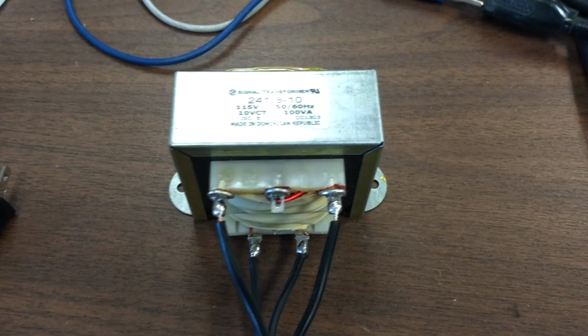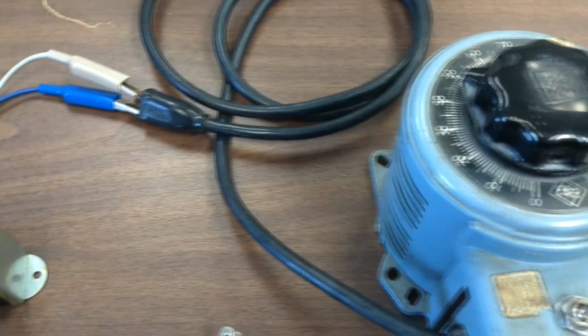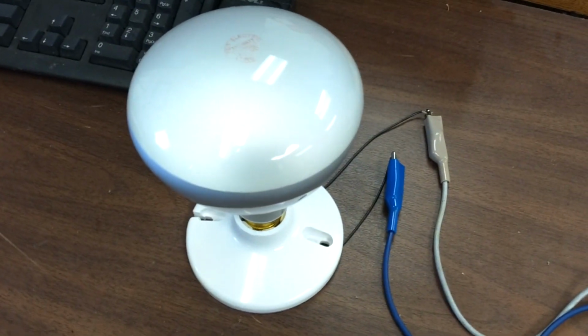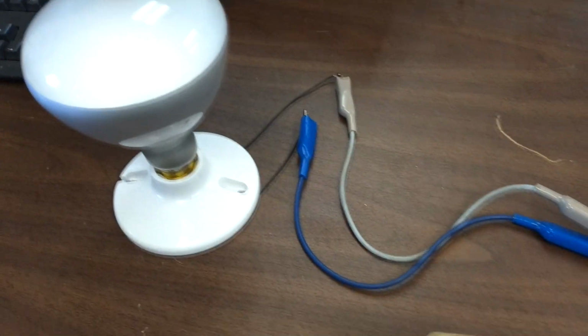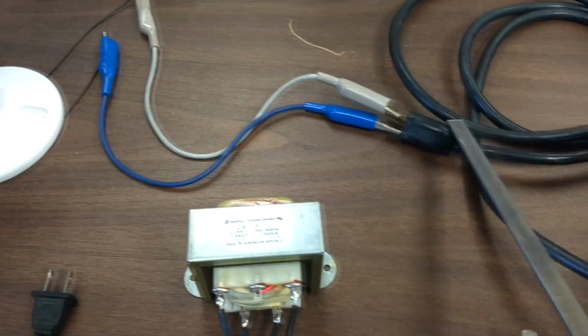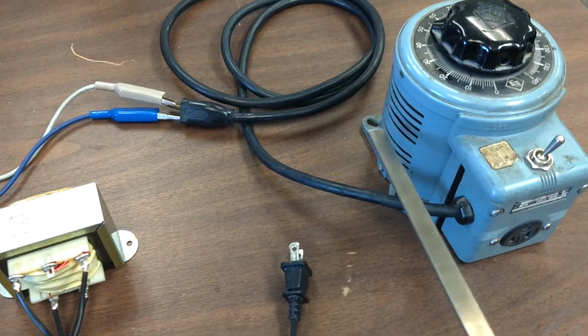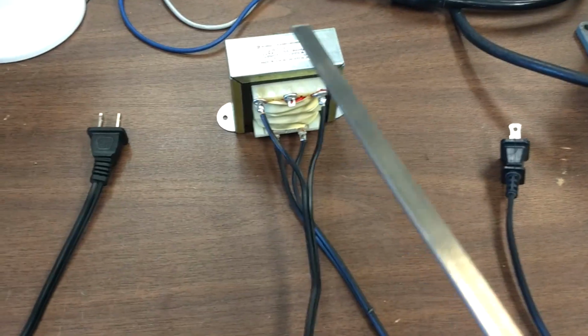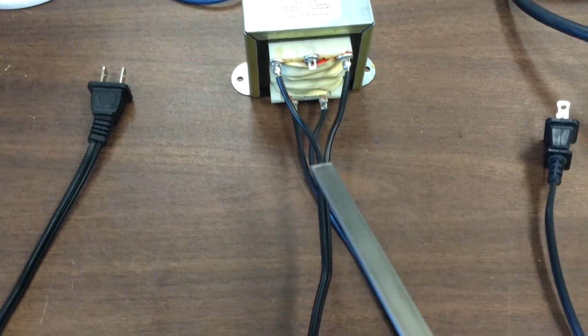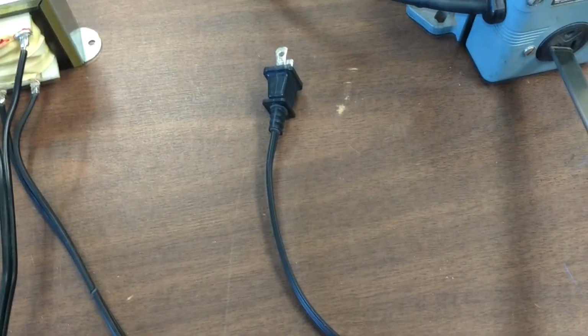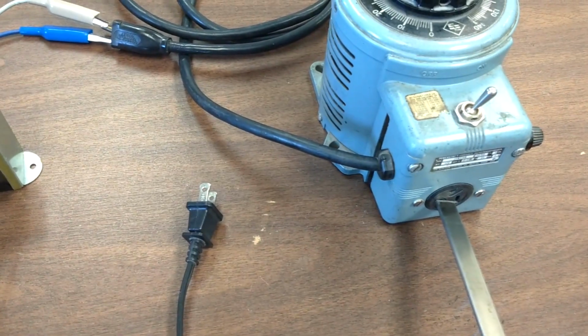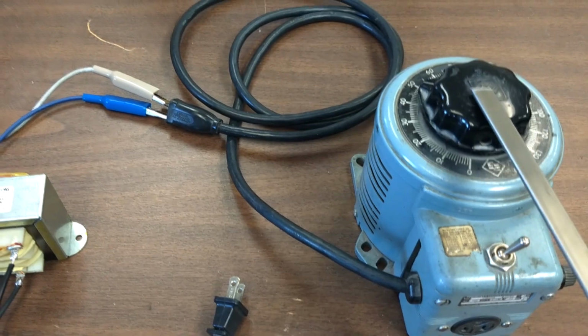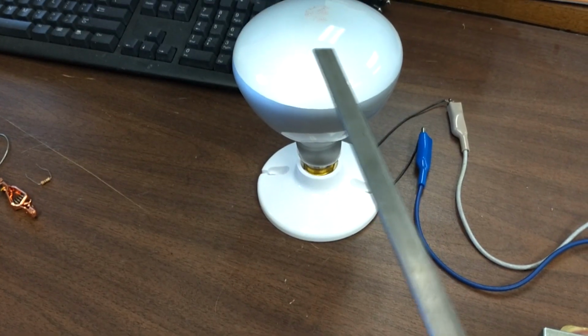Since I don't have that, I'm going to use this variable transformer to match the load to a 150 watt lamp. We're going to connect the lamp to the input of the variable transformer, and the input of our transformer under test we will plug into the output of the variable transformer, and then we should be able to adjust the turns ratio until we get a 100 watt load into this lamp.